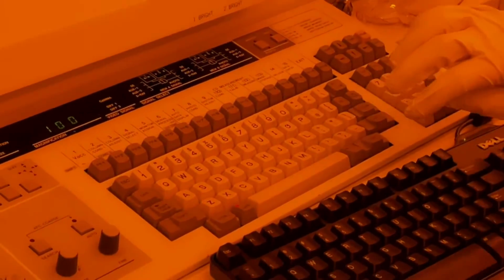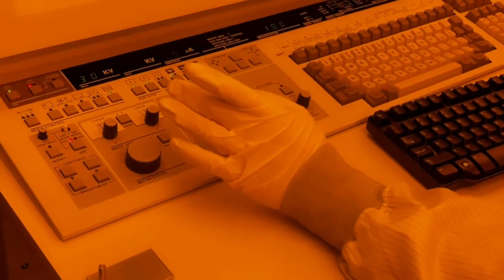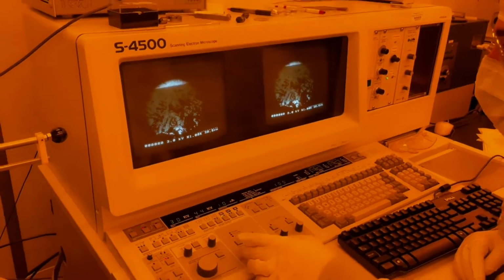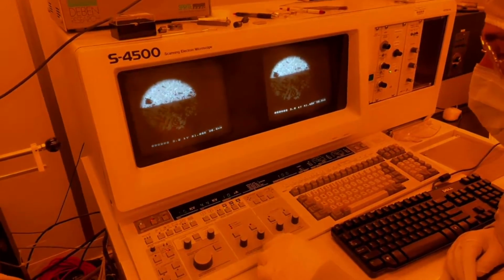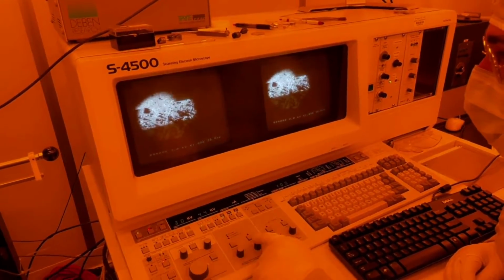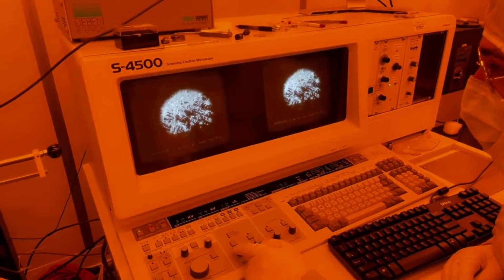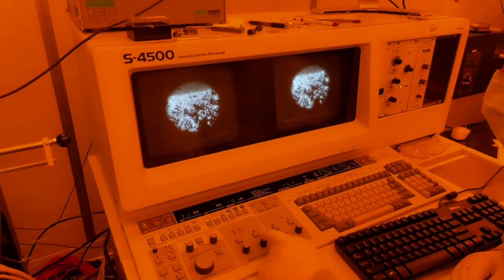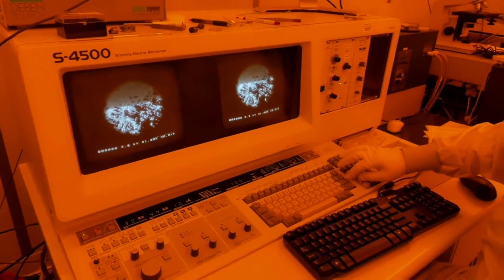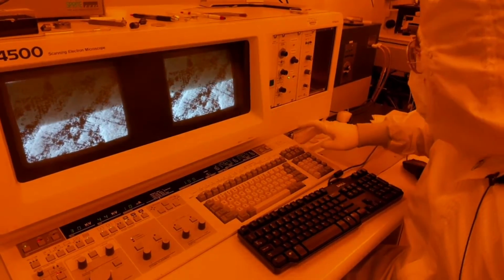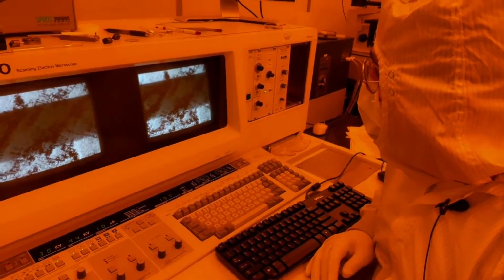So the first step is the beam alignment. Zoom in until your beam is visible on the screen. Now you want this circle to be in the center of your screen. So use the X and Y stigmation alignment to bring that beam to the center of your screen. There we go. Now it's at the center. Press enter. Now we're going to go on to the aperture alignment.